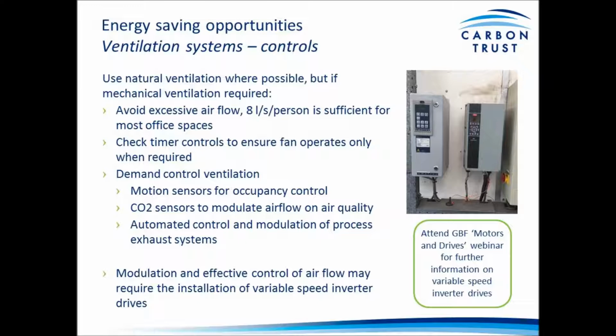So moving on to ventilation systems. Ideally with ventilation systems, you can use natural ventilation because it's free. But if you are looking to use mechanical ventilation, make sure it's effectively sized and you're not overly ventilating the building. So avoid excessive airflow. 8 litres per second per person is sufficient for most office spaces. Some situations do require higher flow rates, in toilets, etc.